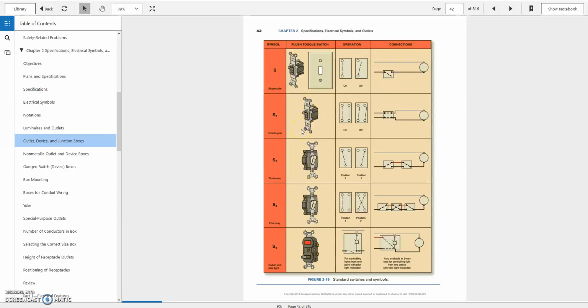So when you see yoke, you can almost think of one device that fits in a single gang spot would be one yoke. So most of your devices are one yoke. You get the larger devices, think of a dryer receptacle, maybe that's going to be a two yoke situation at that point. Then the other item in here that I think is kind of a tough section.